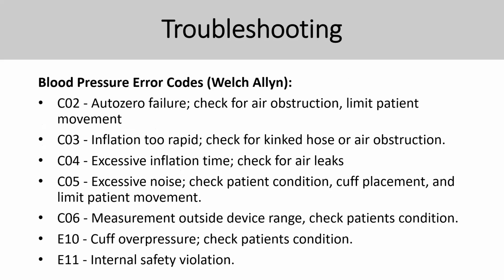Okay, troubleshooting by using error codes. These are based on the manufacturer's error codes. C02 is auto zero failure, all these. Each brand and model has its own error codes. So remember, you sometimes need to open your service manual or user manual to troubleshoot.